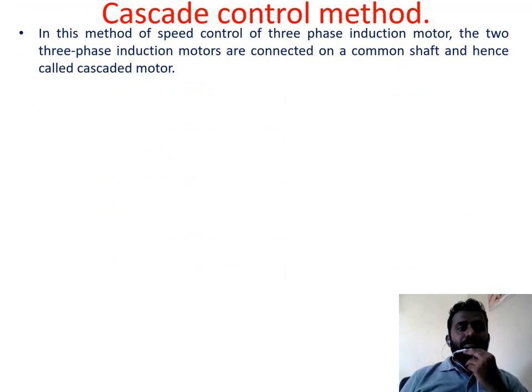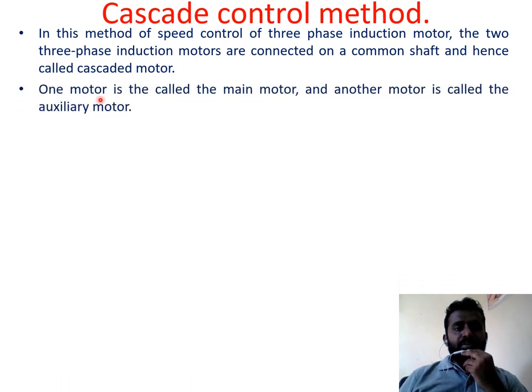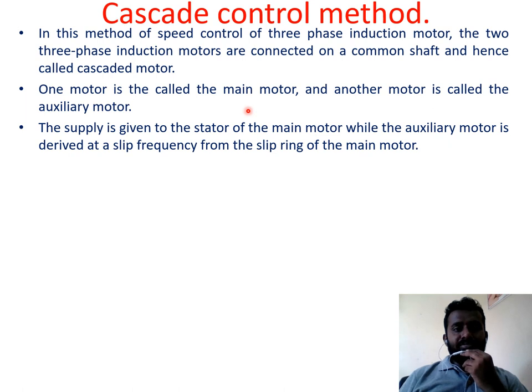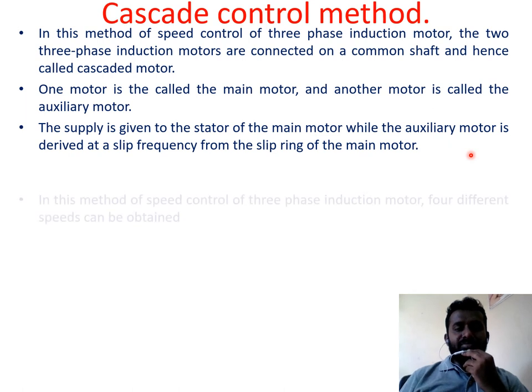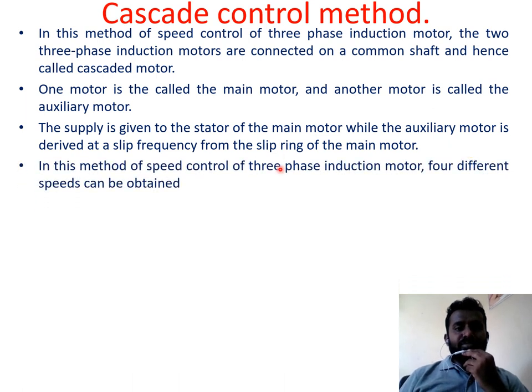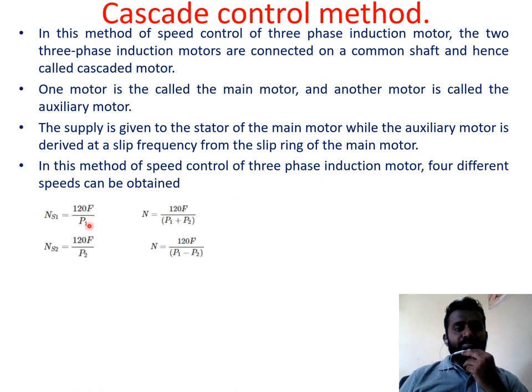Cascade control method: in this method, two induction motors are connected on a common shaft and hence called a cascade motor. One motor is called the main motor and the other is called the auxiliary motor. Supply is given to the stator of the main motor, while the auxiliary motor is driven at slip frequency from the slip ring of the main motor. Four different speeds can be obtained: 120F/P1, 120F/P2, 120F/(P1+P2), and 120F/(P1−P2).